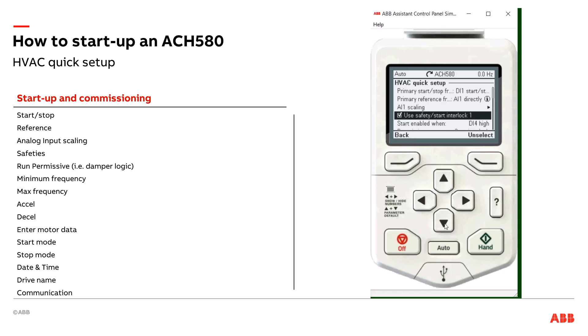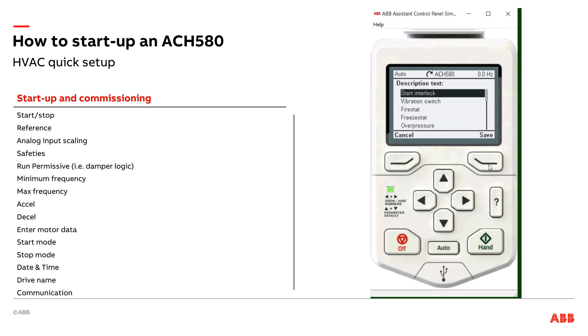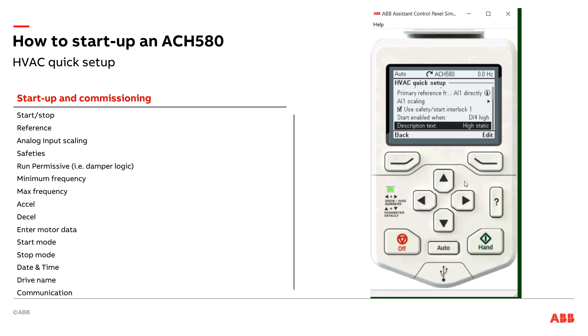Now it asks me: do I want to use a safety or not? I can uncheck that box by hitting unselect if I had no safeties. Factory default has a safety assumed on digital input four, which is what you're seeing right here. I can also change the text label for that safety. So what I'm going to do is go in here and instead of having it say 'start interlock,' I'm going to change that to say 'high static safety.' So now when that safety opens up, it'll actually tell me that the high static is open and that's why I'm not running — great to add that extra description there.